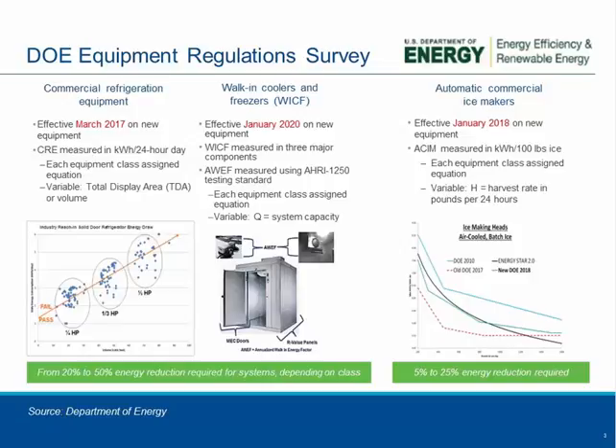That has since then gone back to the ASRAC Working Committee, which is now pushed out in terms of levels on the low temp side, and its effective date is now going to be January of 2020. Unlike commercial refrigeration equipment and automatic commercial ice makers, the walk-in coolers and freezers are really measured on the refrigeration system side and what's called the AWEF, the annualized walk-in energy factor.